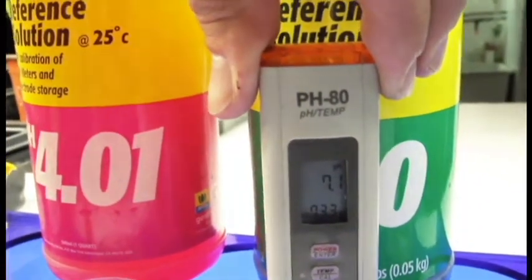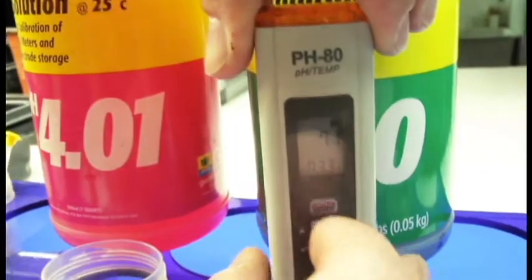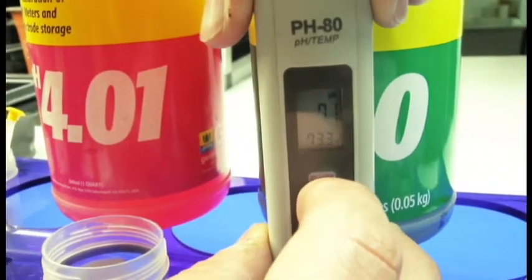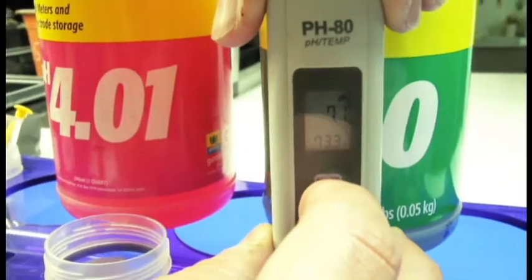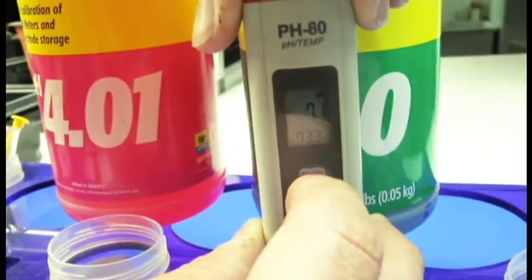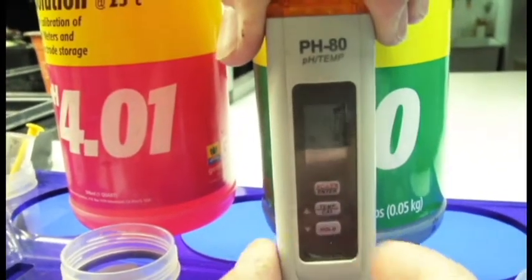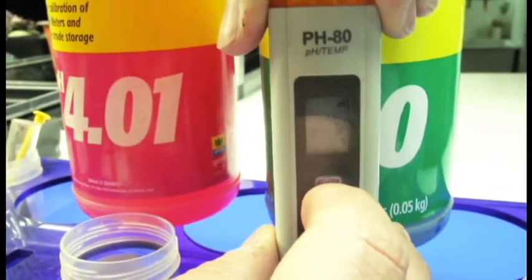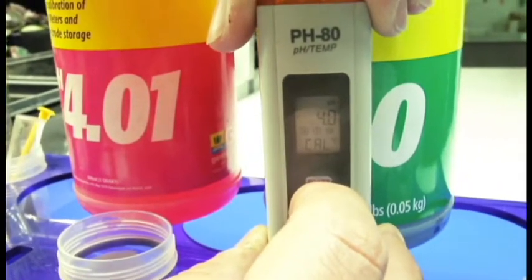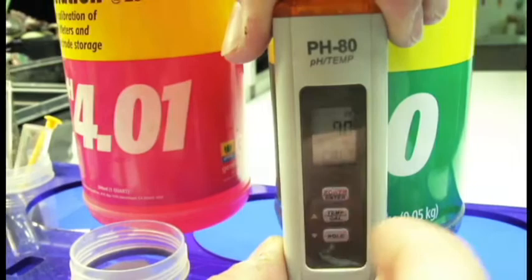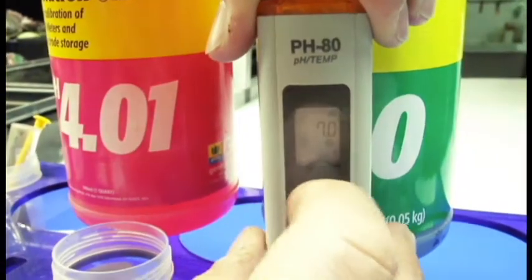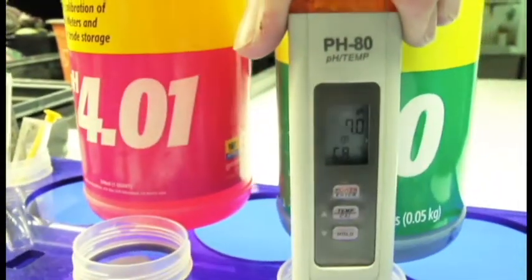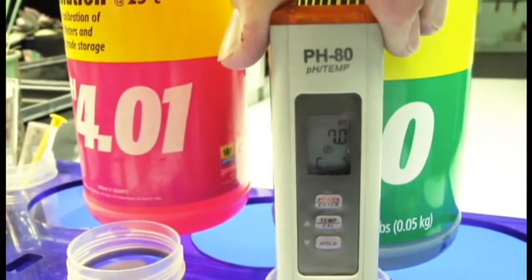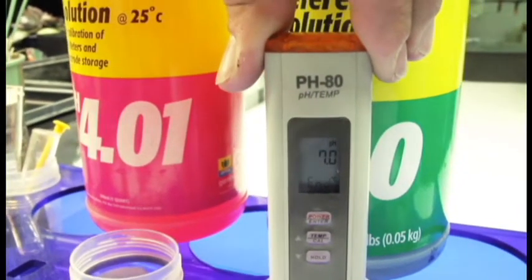Alright, so now I'm going to hold down this center button again, and I'll show you that process I was talking about. I'm going to hold it down until it blinks at me, and it's going to tell me it's in 7.0. If it was in the wrong one, I can press this center one and it'll go to 10.0, then 4.0, and then 7.0. But I am in 7.0, so I'll let it stay there and I'll hit that top button for enter. Now it's calibrating and it's going to say the word end to tell me that it's done.